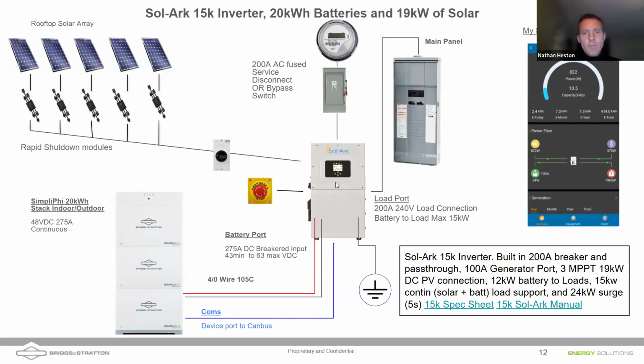And then there's a rapid shutdown by code. This has to be accessible by emergency workers. Like it should be on the outside of the house, and this will shut down all production from the inverter. You're looking at a disconnect here. So you do have to have a service rated disconnect between the meter can and the inverter. I know there's been some confusion around that. And in fact, we would even recommend this be a 3-way switch, so you could potentially bypass the inverter if you ever need to do work on the solar system. You can keep the loads alive for the house. So this is a simple example, and we're showing it here with the Sol-Ark 15K and with Briggs & Stratton 3.6 batteries, making a stack of about 20 kilowatt hours there.